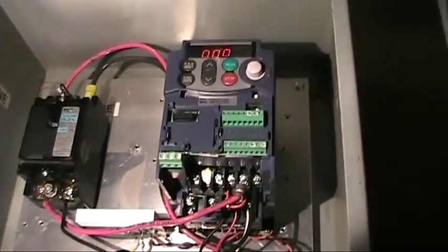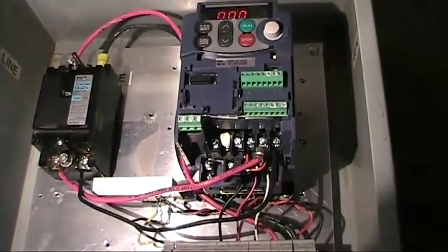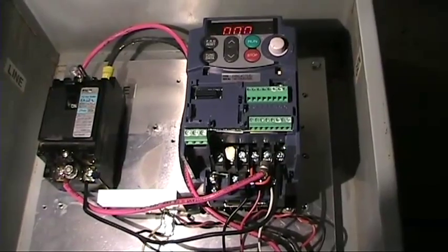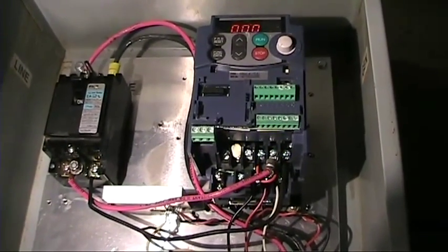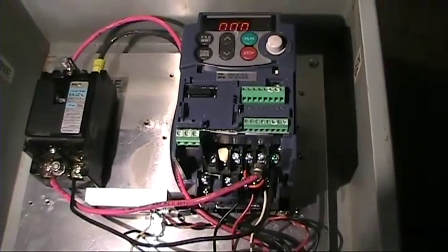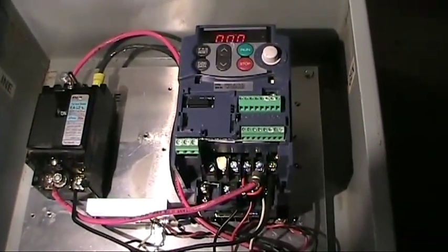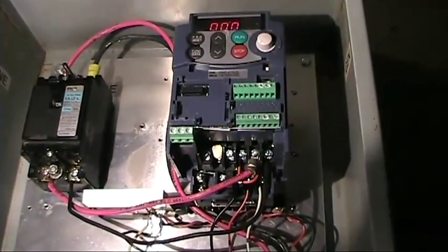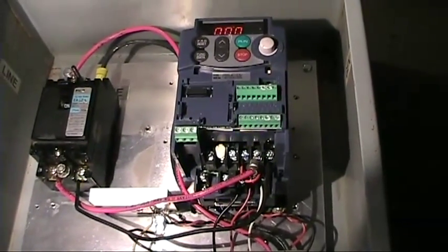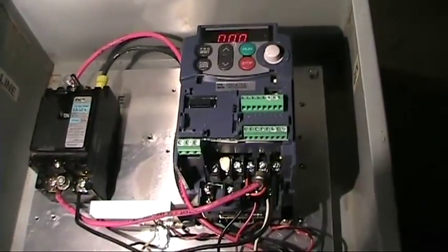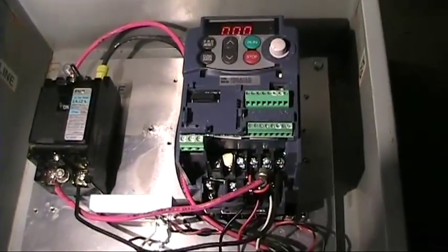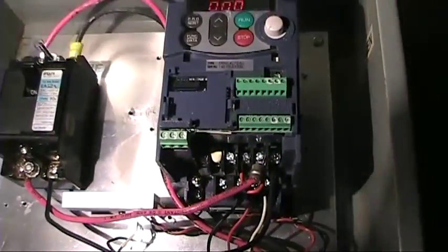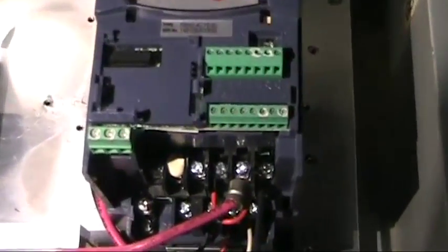The variable frequency drive sometimes is called an inverter. And most people when they think of an inverter they think okay it takes batteries, DC, and converts it into AC. The variable frequency drive sometimes might confuse people when they call it an inverter because they see it's got an AC input and an AC output. But it really is an inverter. Inside the AC is turned into DC and there's a point of entry for the direct current called the DC bus.